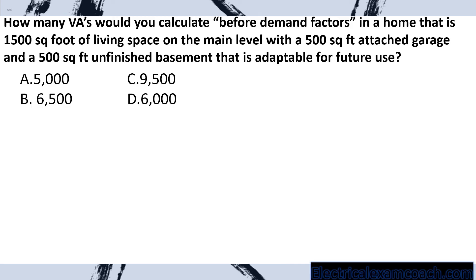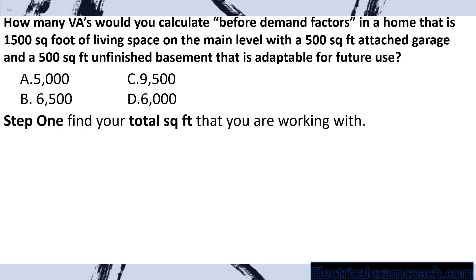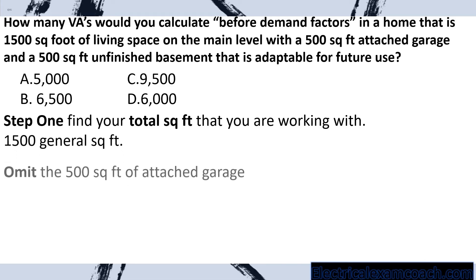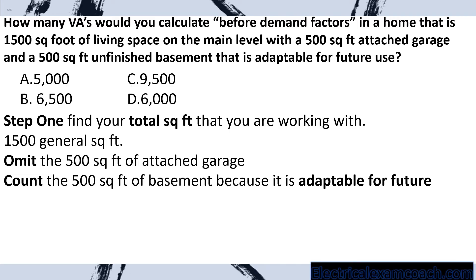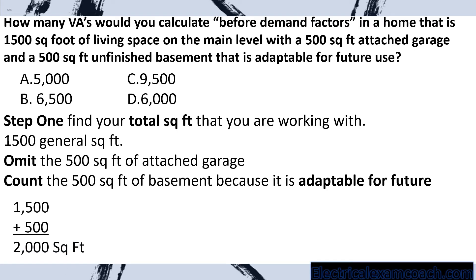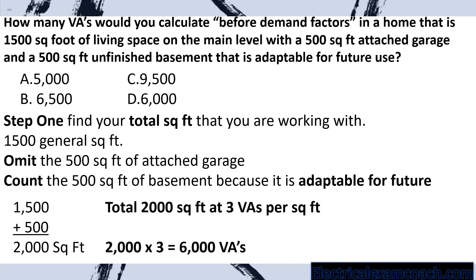How many VAs would you calculate before demand factors in a home that is 1,500 square feet of living space on the main level, with a 500 square foot attached garage and a 500 square foot unfinished basement that is adaptable for future use? Step one: find our total square feet. We count the 1,500 general square feet. We omit the 500 square foot attached garage. We count the 500 square foot basement because it is adaptable for future use. That gives us 2,000 square feet. Then we take 2,000 square feet multiplied by three VAs per square foot and select answer D.